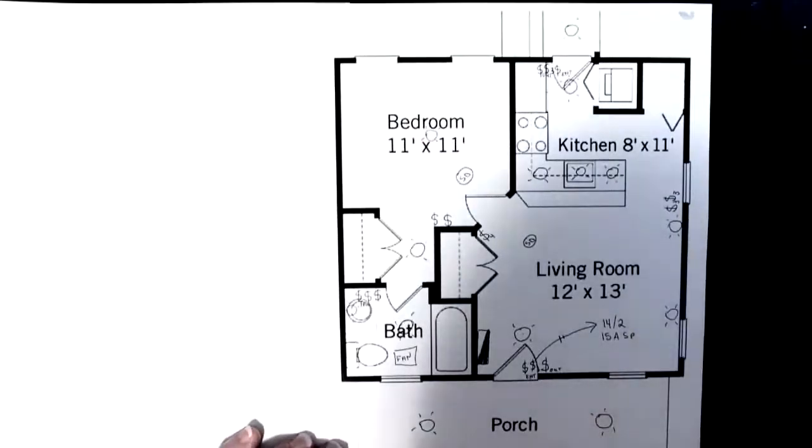Now, rule of thumb is that we only put 12 lights, or combination of lights and smoke detectors, fans, things like that, on one circuit. Nowadays, with LEDs, there are some exceptions, but I don't know whether they're going to use incandescent bulbs in these lights, or LED lights. So I'm going with a maximum of 12 on these circuits.